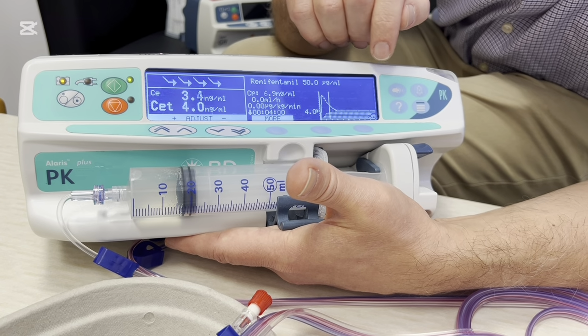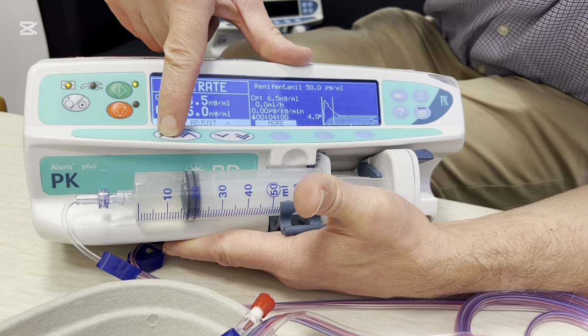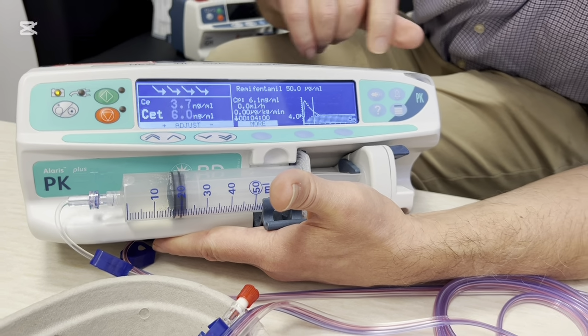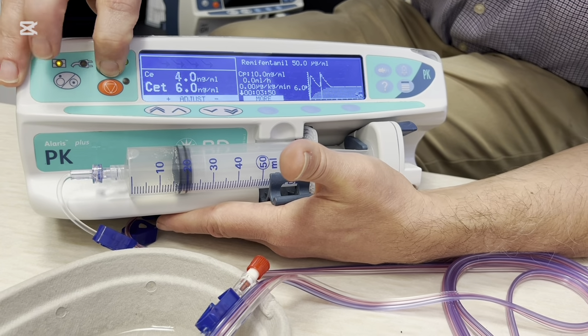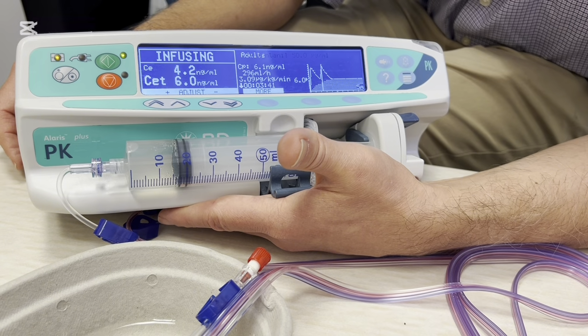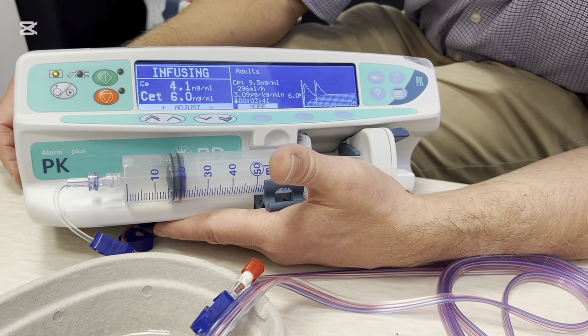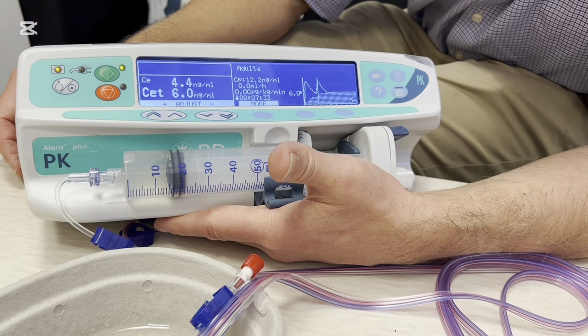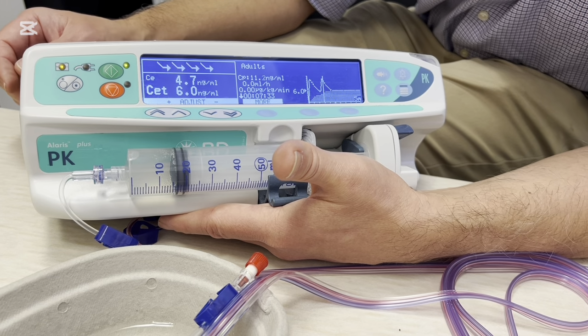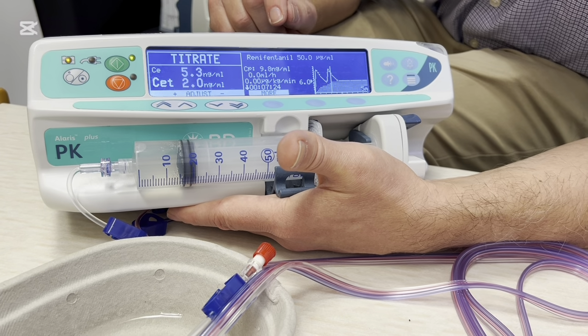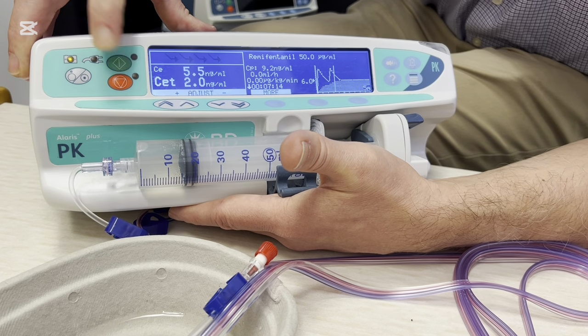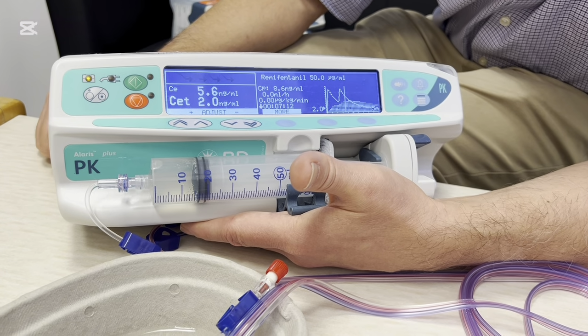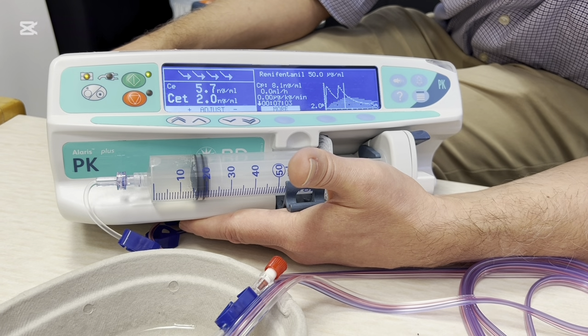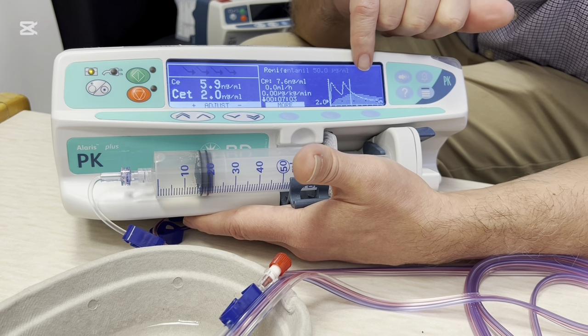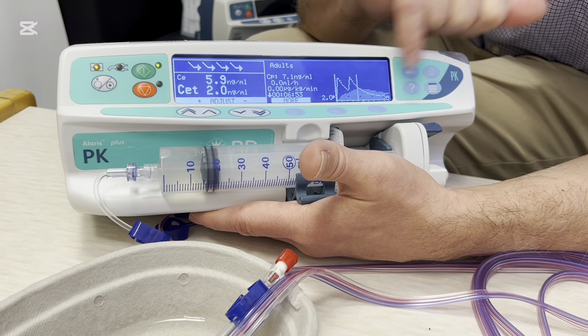If you want to change the rate on these devices, so we'll increase the effect site that you want to achieve, just change the number, press the green to confirm. And we'll then bolus the syringe accordingly. And then slowly wait for the effect site to catch up. If you decide to decrease the rate, then again, you're titrating it down. You still need to press to confirm, otherwise it'll alarm. And now it's just going to enter a prolonged period of not infusing whilst it waits for the plasma or effect site concentration to decrease. And in the meantime, it's going to graphically display what the target is and potentially how long it's going to take to get there.